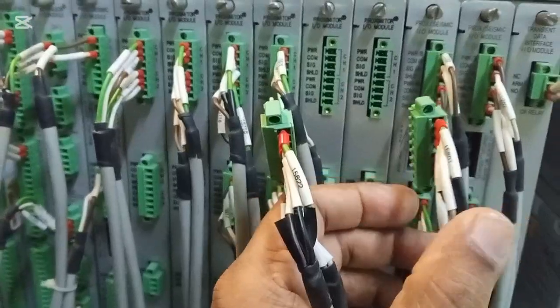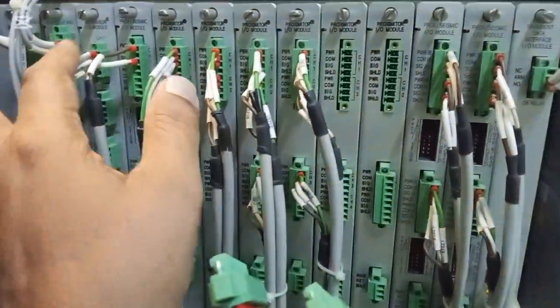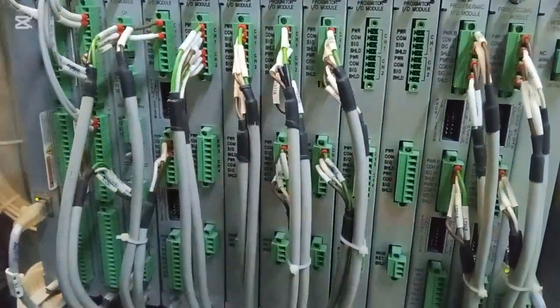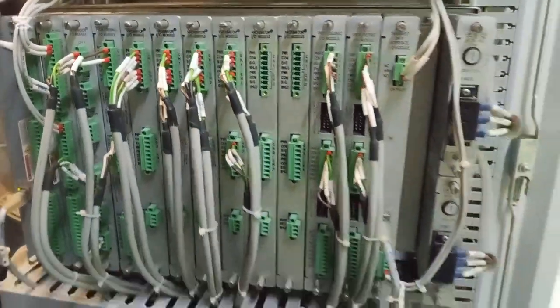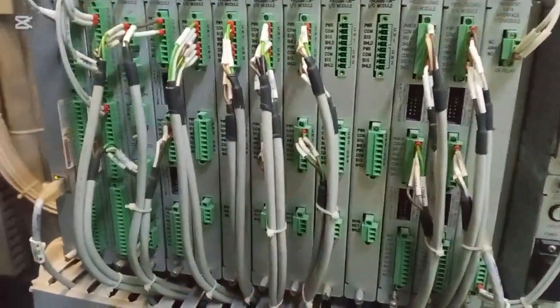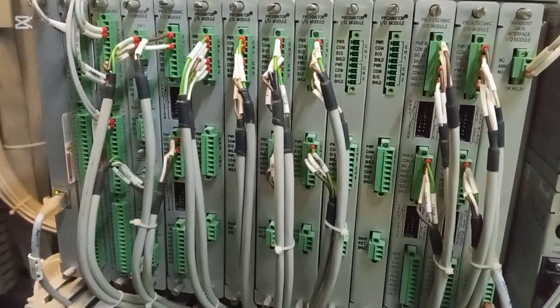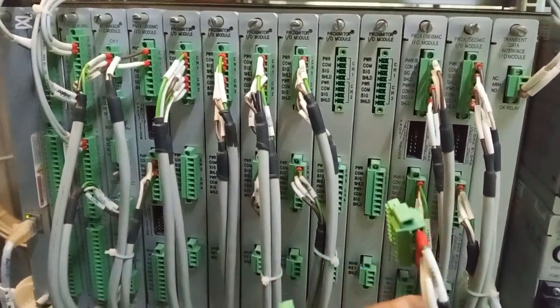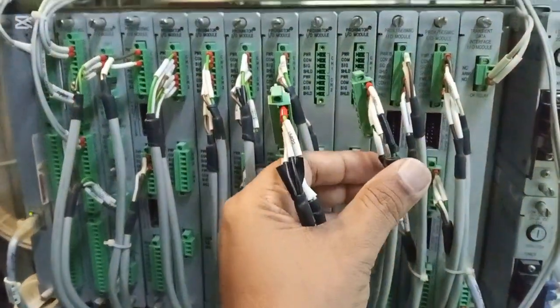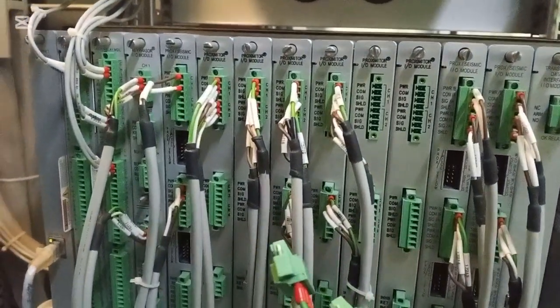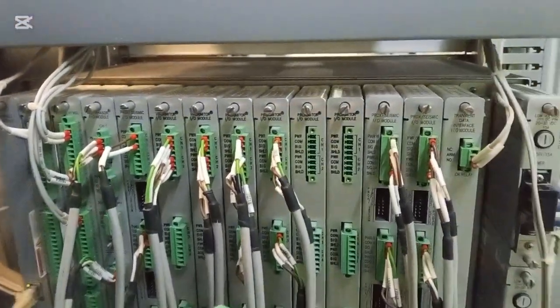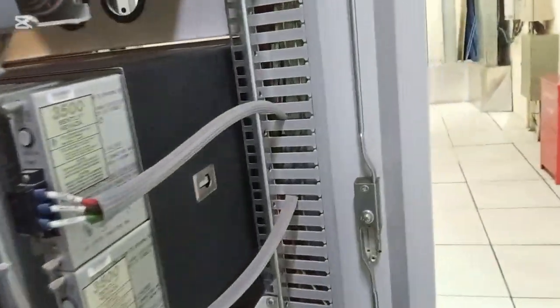At first we identified which sensor is connected with the Bentley Nevada system, identified different sensors at different cards, opened the sensor, then reconnected it, but the problem still exists.